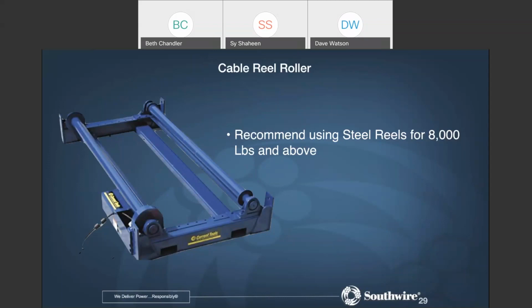This wooden reel is not meant to be turned that much on its flange. And the heavier the cable, the more it wobbles, and the more issues you'll have, because like I said, the flange is not really made to take that abuse. Whereas if you have a steel reel, these really work very well with steel reels. Especially on heavy reels, this is good on heavy reels.